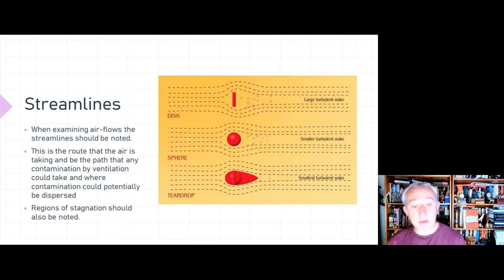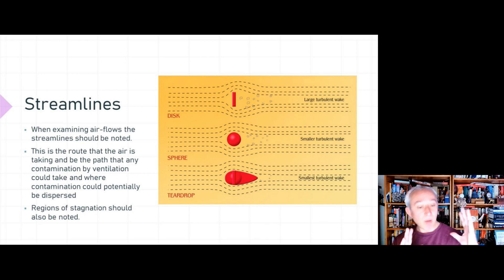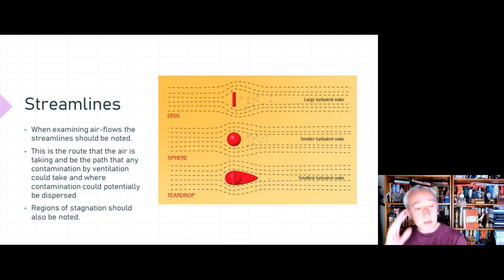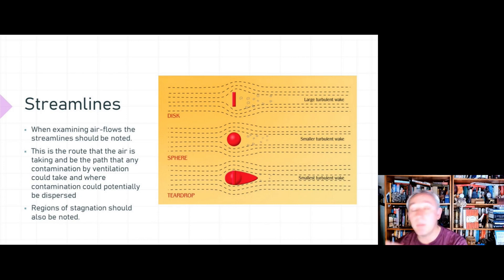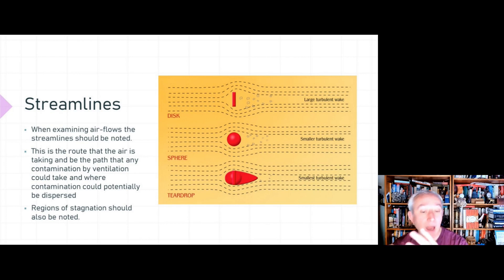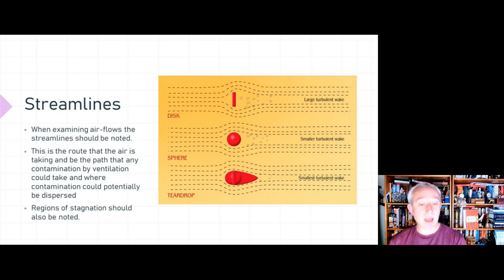When examining airflows, streamlines also need to be noted. A streamline is defined as the route that the air is taking, and it will be the path any contamination could take — what might be called convective transport. When a streamline meets an object and causes turbulence, contamination could potentially be dispersed through turbulent diffusion. The study of precise flow direction also helps us find regions of stagnation, which can often occur in front of machinery and by work surfaces perpendicular to the airflow.